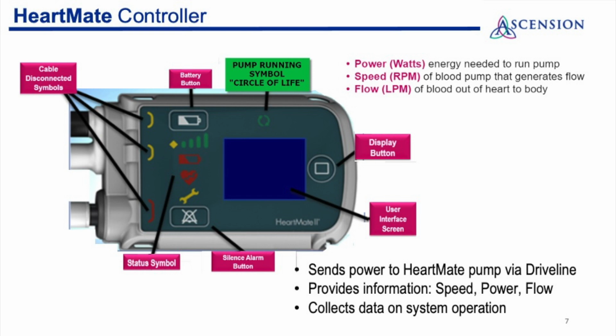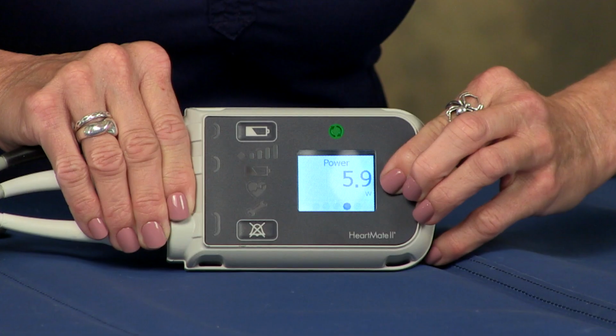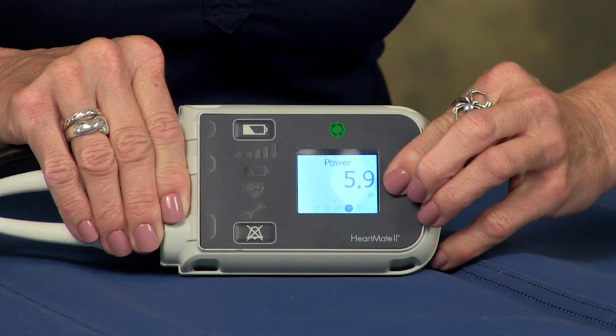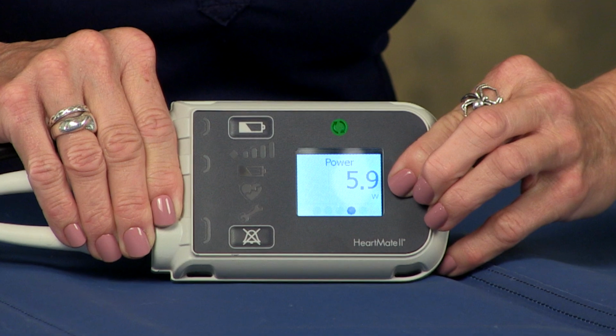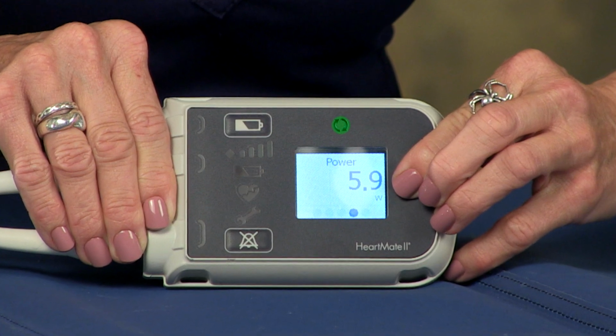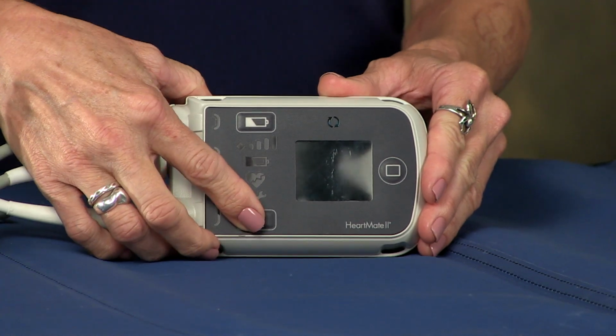Now for the HeartMate controller. One of the first things to check for is what we call the green circle of life. When it's illuminated, we know the pump is running, and it's one of the first things to check if an alarm is occurring. This is in addition to actually putting a stethoscope on the patient's chest and listening for the VAD pump hum. If an alarm does occur, here is the alarm silence button to help you think clearly and hear the VAD coordinators when they're trying to help you troubleshoot.